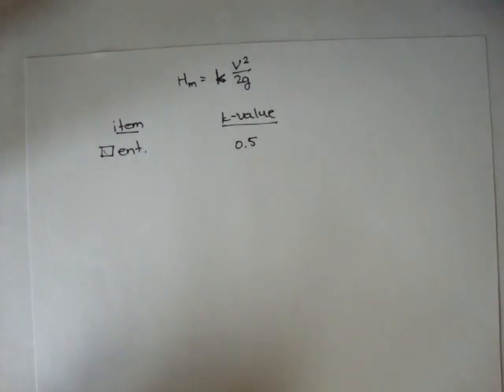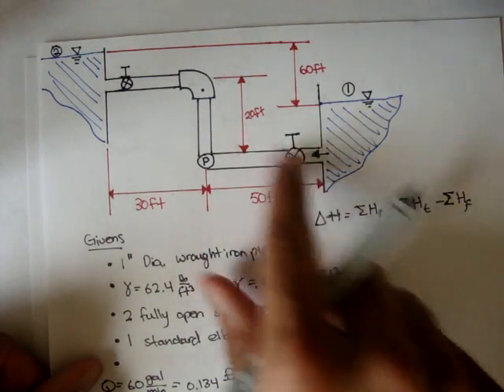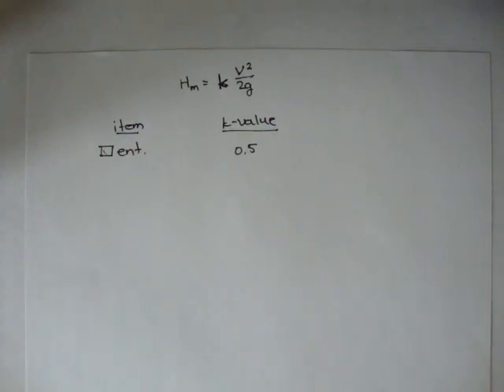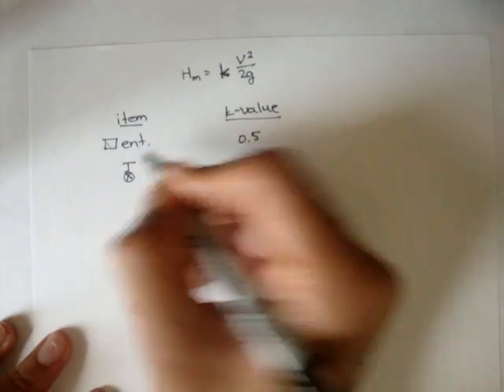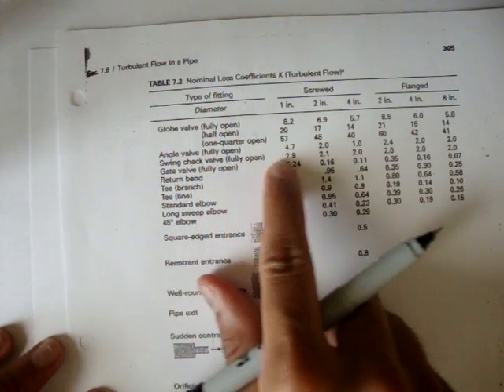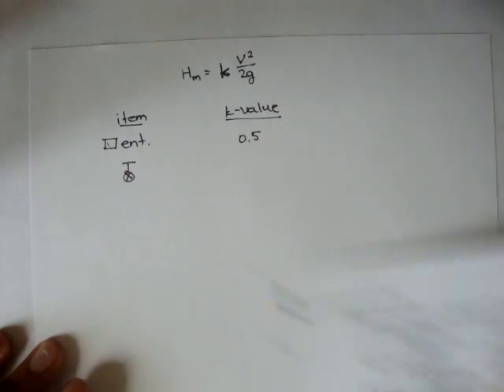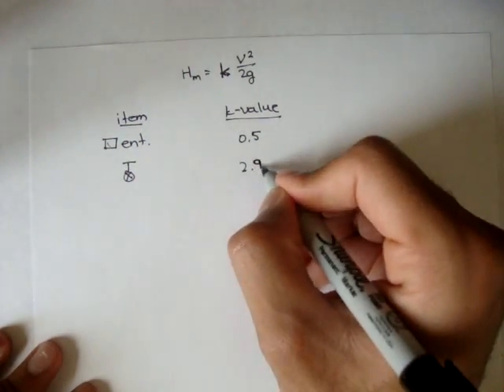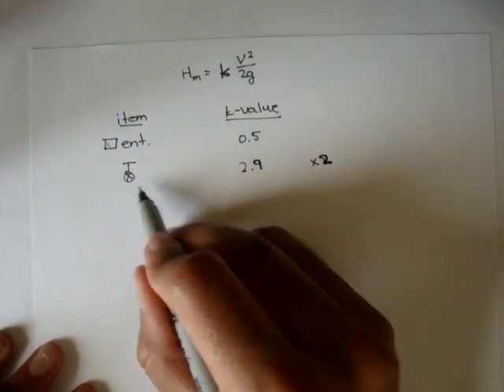If we continue, we have two fully open swing check valves. A fully open valve - its k value on the table here, swing check valve fully open and one inch, is 2.9. So we'll write that there. And just to clarify, there's - I'll say two, or times two, meaning there's two of those valves.